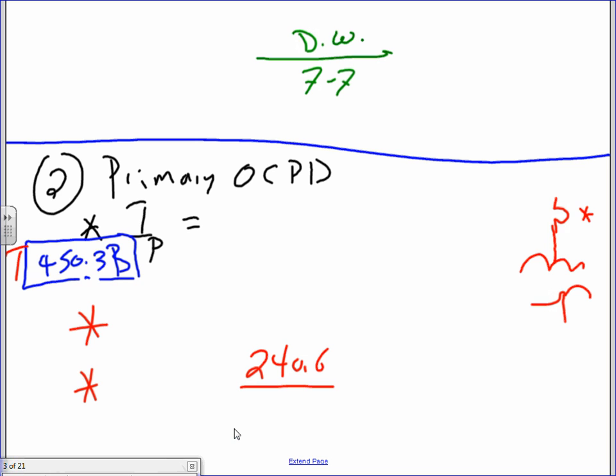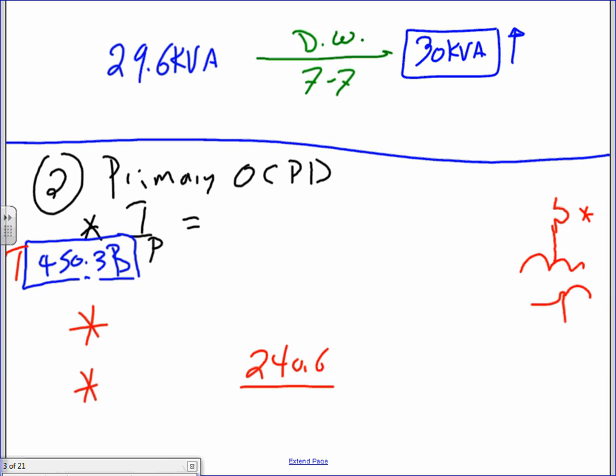So when you go to 7-7, we have 29.6 kVA. This is my demand. Take him to DeWalt 7-7. And Derek, on the left side, when you look at 7-7, it says three-phase full load current amps, and it gives you the kVA. What's the next standard from 29.6 kVA? 30. Everybody got that? So the next standard is a 30 kVA transformer. You go up, right? You're not going to go down. The next standard transformer that you need for this project is 30.